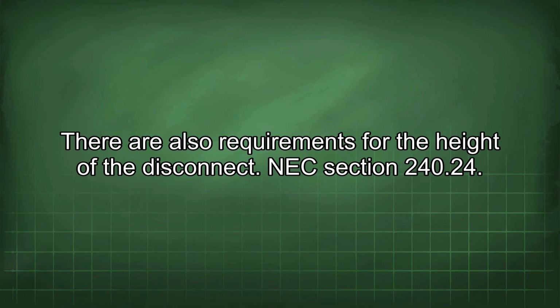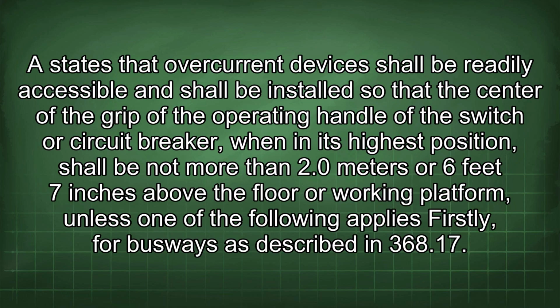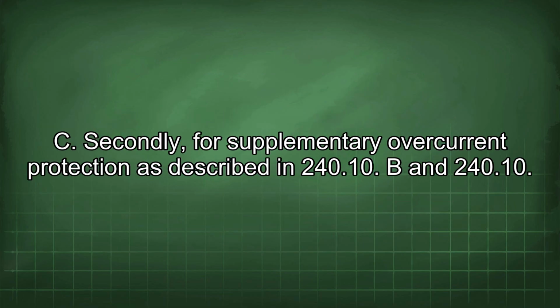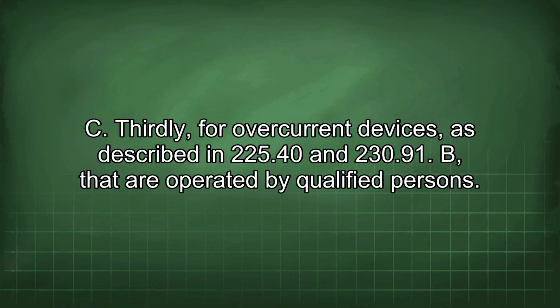NEC Section 240.24 states that overcurrent devices shall be readily accessible and shall be installed so that the center of the grip of the operating handle of the switch or circuit breaker, when in its highest position, shall be not more than 2.0 meters or 6 feet 7 inches above the floor or working platform, unless one of the following applies: firstly, for busways as described in 368.17(C). Secondly, for supplementary overcurrent protection as described in 240.10. Thirdly, for overcurrent devices as described in 225.40 and 230.91 that are operated by qualified persons.